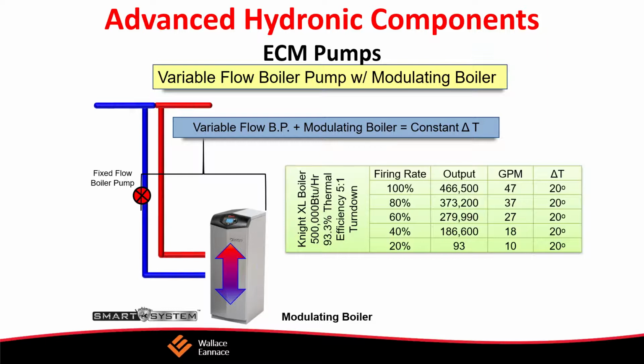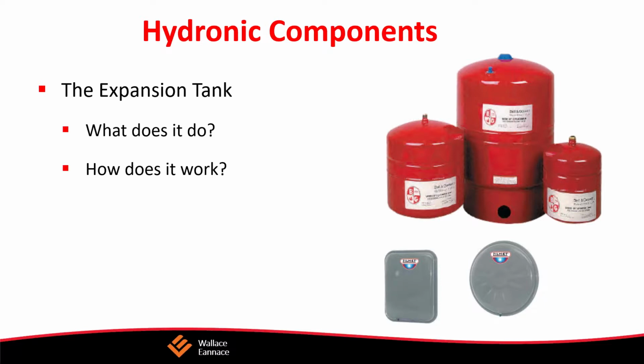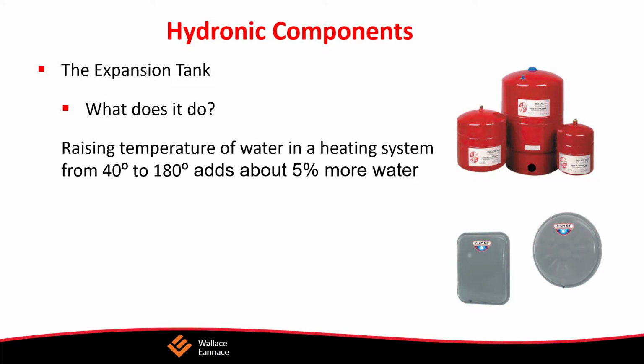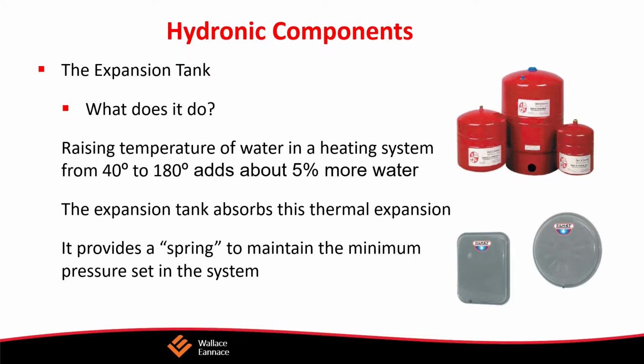One of the important points of ECM pumps is that when you have a modulating boiler, generally speaking, most applications are using a fixed flow pump with the modulating boiler. Here you can see a 500,000 BTU modulating boiler with a 5-to-1 turn down ratio. We have a fixed flow pump, which has been set for a 20-degree delta T at 100% firing rate. At 100% firing rate at 93.3% efficient, its output is going to be 466,000 BTUs. You'll have a 47 GPM flow rate, and the delta T will be 20 degrees.